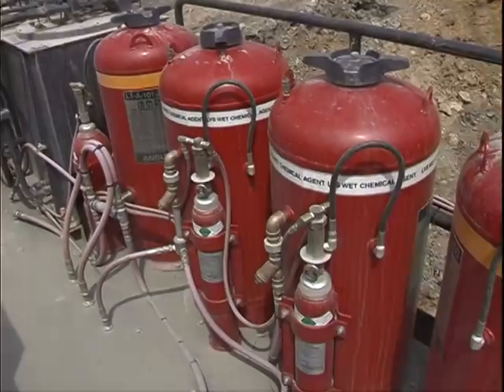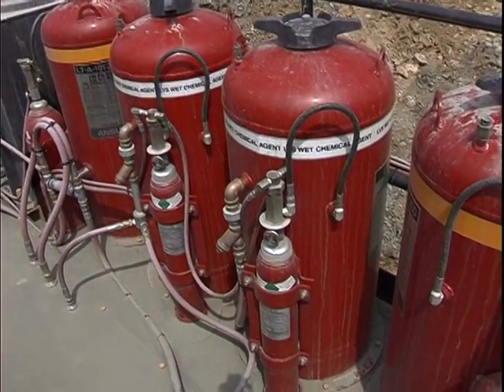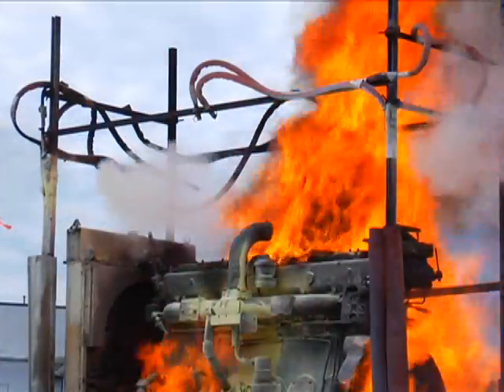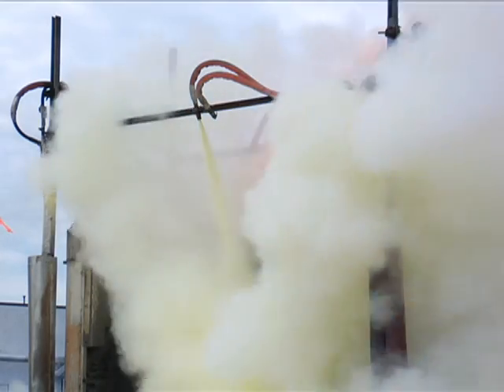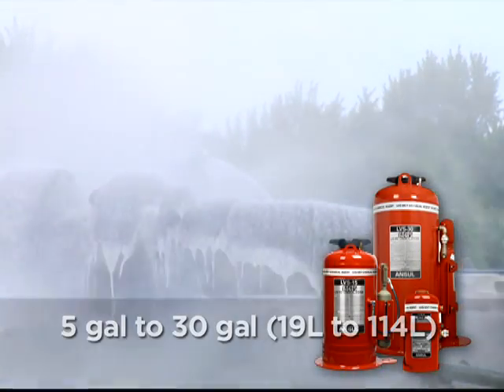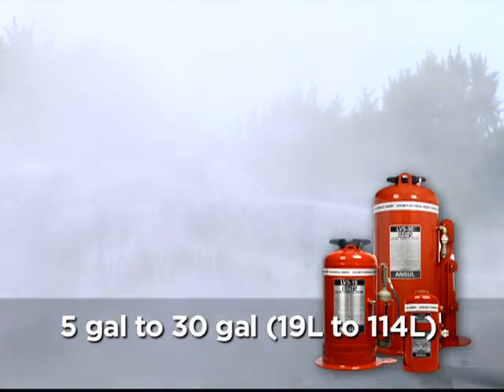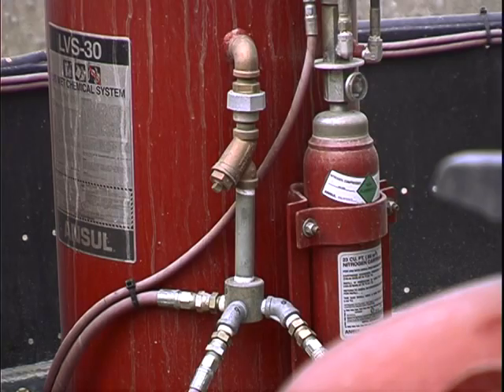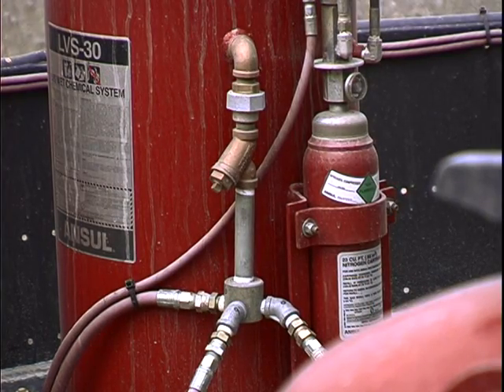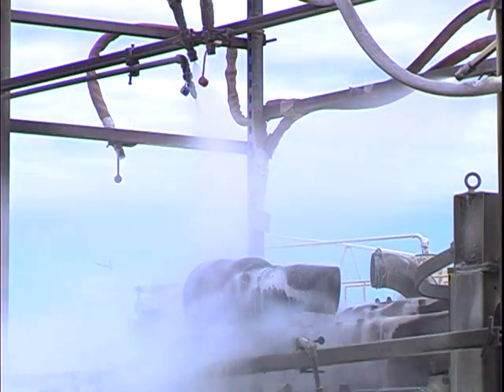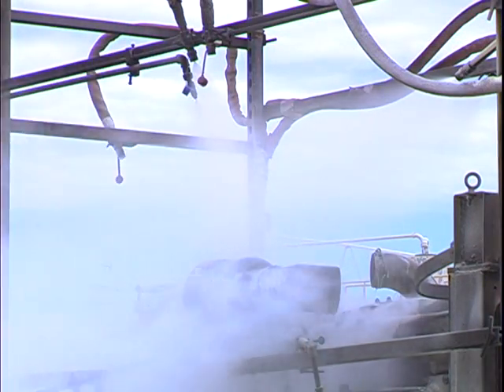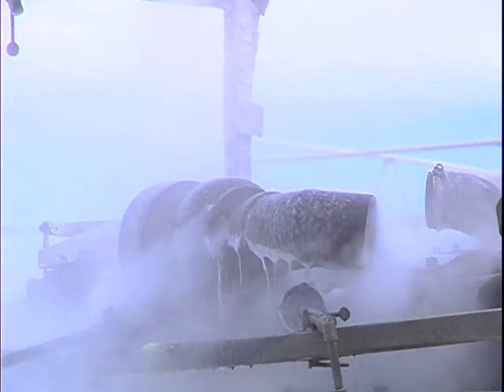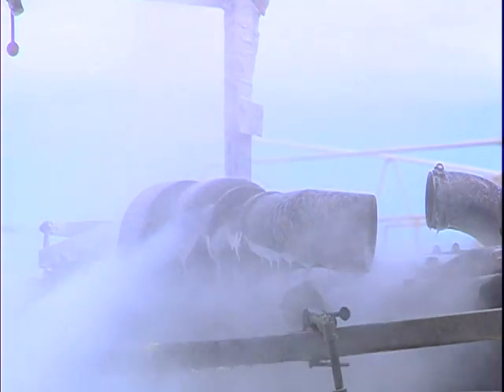To help prevent fire reflash, you can add the LVS liquid agent system to the A-101 system, creating a powerful dual agent system. The LVS liquid agent system is stored in 5, 15, or 30-gallon tanks with an independent nitrogen supply for discharge. The LVS response is phenomenal, with a cool-down rate approximately 6 times faster than dry chemical.